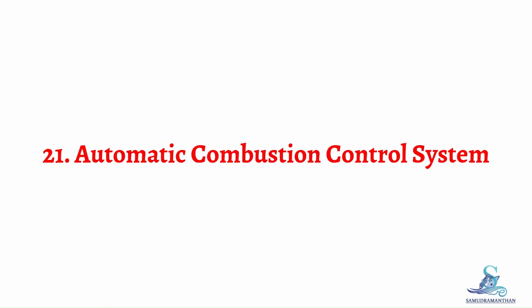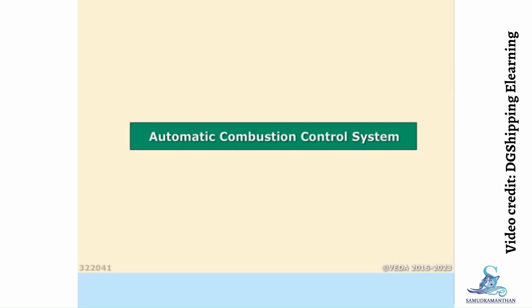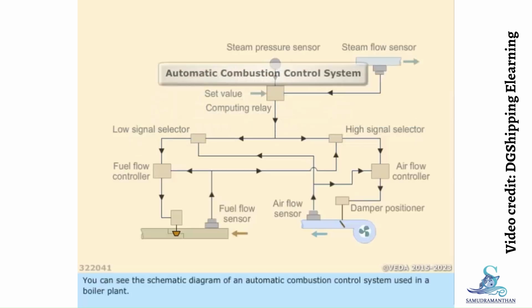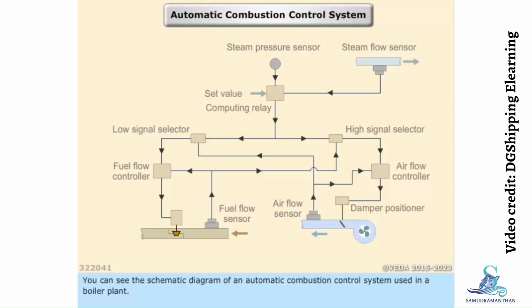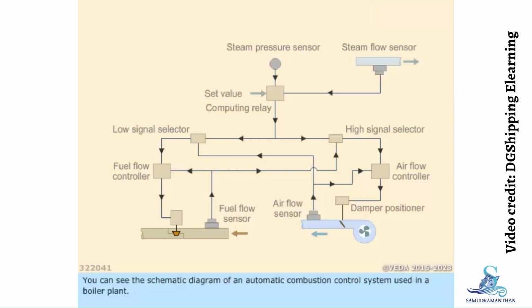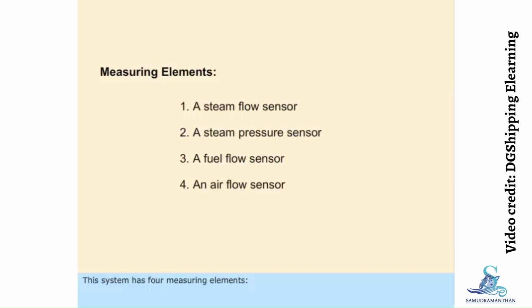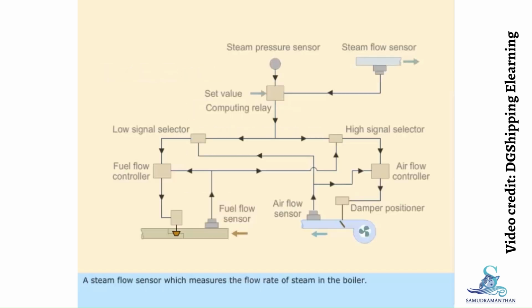Topic 21. Automatic Combustion Control System. You can see the schematic diagram of an automatic combustion control system used in a boiler plant. This system has four measuring elements. A steam flow sensor, which measures the flow rate of steam in the boiler. A steam pressure sensor, which measures the pressure of steam in the boiler. A fuel flow sensor, which measures the fuel flow in the boiler burner. An airflow sensor, which measures the air to the boiler.